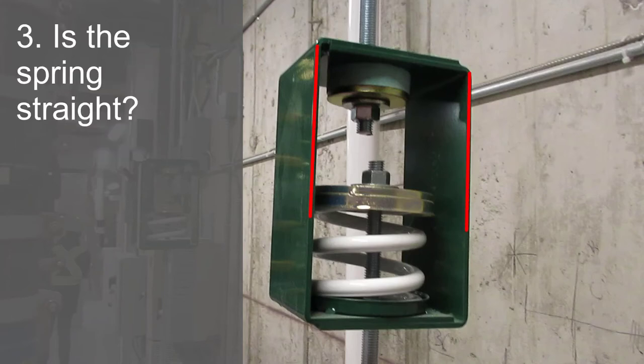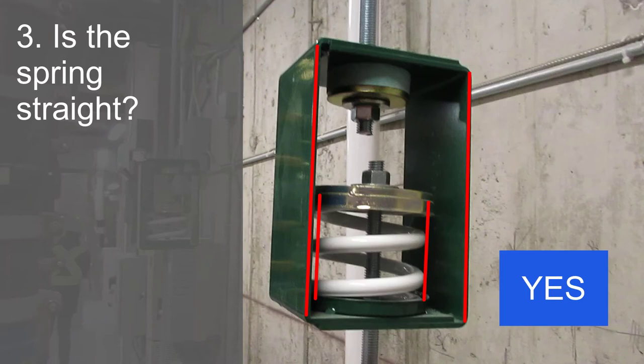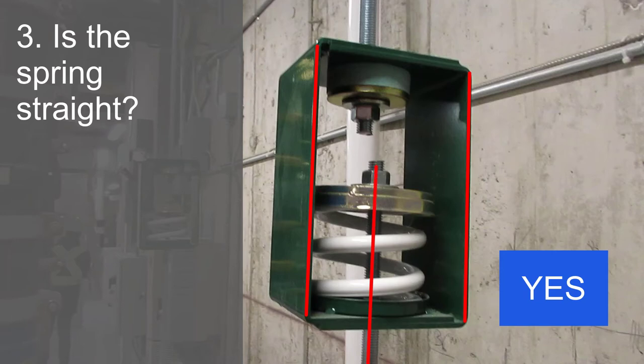Next, is the spring straight and not bent over? Yes. I have seen installations where the spring was not sitting flat on the bottom of the housing and the lower hanger rod was significantly off-center, due in part to being smaller than the max rod diameter size, bending the spring to one side so that it may contact with the side of the hanger box. This spring is straight and not in contact with the box sides. The lower rod is smaller than the maximum allowable 1 inch diameter rod size, but it is roughly in the center of the spring compression cup.